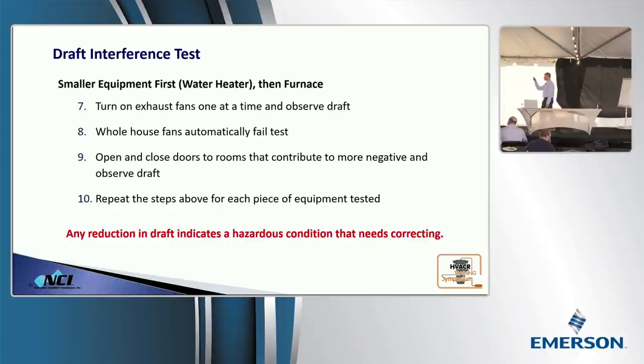At no point should that ball go down. Start to kick on other exhaust fans. See what's happening. Any reduction in draft, whenever you see the ball go down, that's the fan that's interfering with combustion air. Sometimes it's a combination, sometimes it's just one, like the blower and the furnace. But the draft readings are guiding you to what's interfering with your combustion problems.